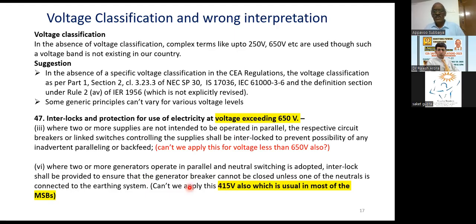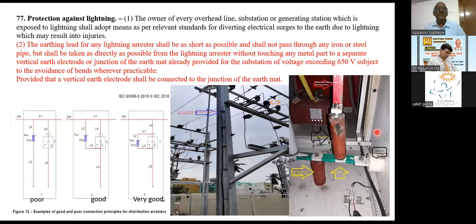See, we have seen a lot of LT generators with 415 volt for multiple things. It's applicable for these things. So these give scope for the implementer or the contractor to interpret wrongly. And protection against lightning, because this is the thing we are abusing, lightning protection, is the important thing. But the regulation has given some clear measures. The owner of every installation shall adopt means as per relevant standards. What's the relevant standard? As per IEC 60099.